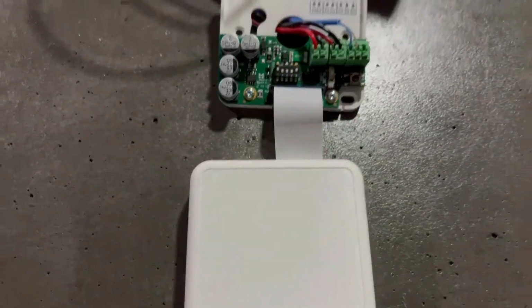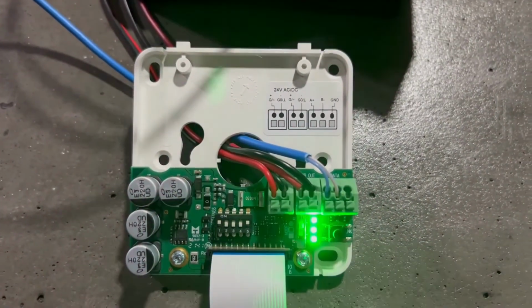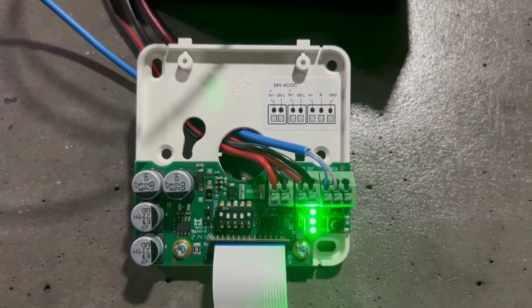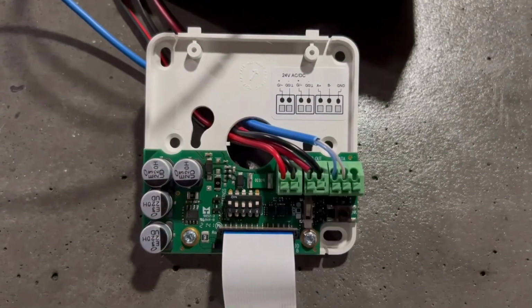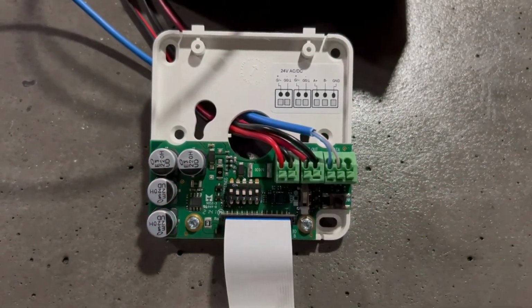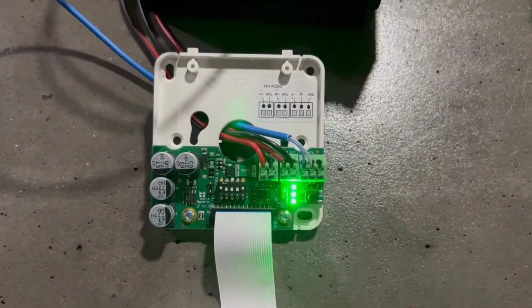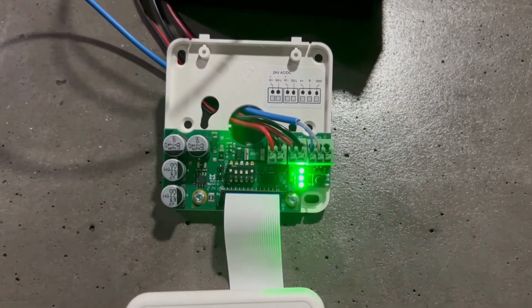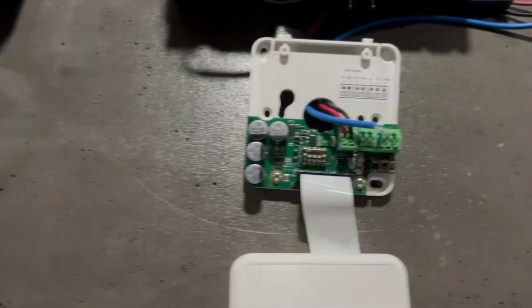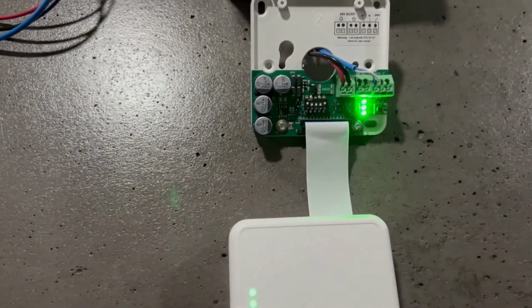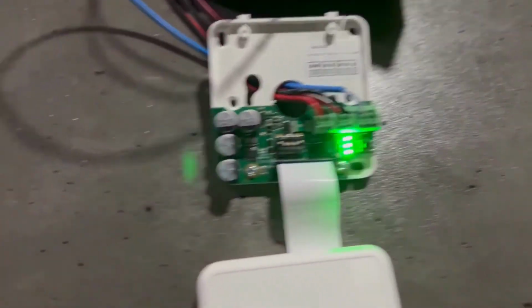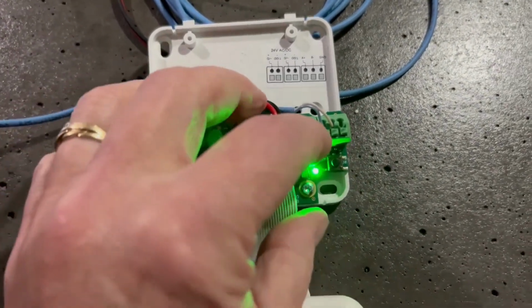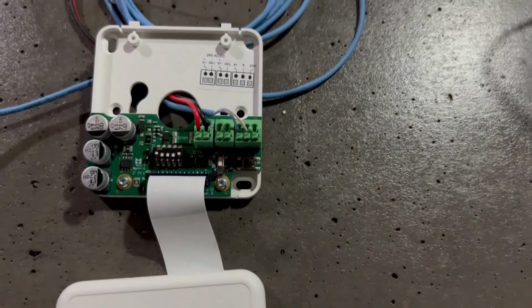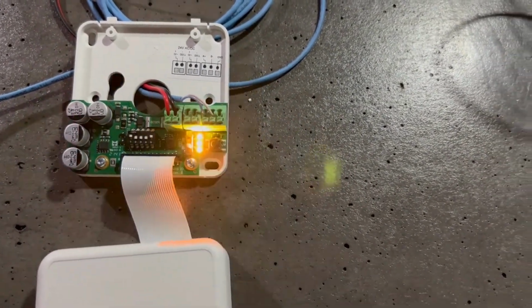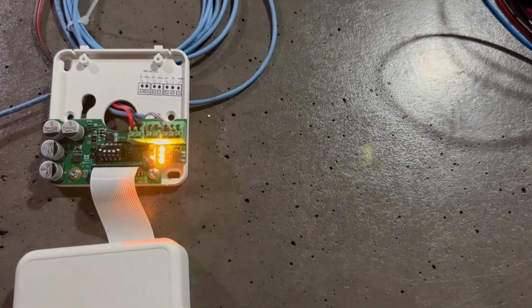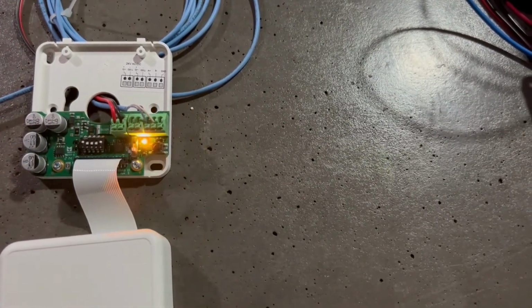The first one here is all set, and the LEDs, the way they work is on a node. Top LED green is node, and amber would be gateway, so this would be a node. The middle LED is going to show signal strength. Green is good, red would be bad, and the third's going to be the MSTP communications. Green meaning there's communications. So right now the triple blinking means that they are all set up with the mesh. So now to lock that in, we go back to the gateway and we move it to the bottom position, which then secures that setup, and it will set up the LEDs appropriately for a fully set up network.